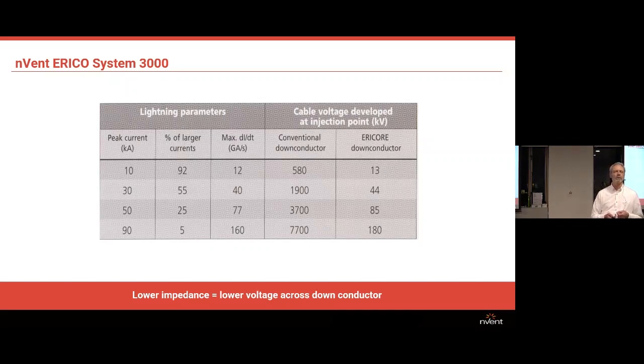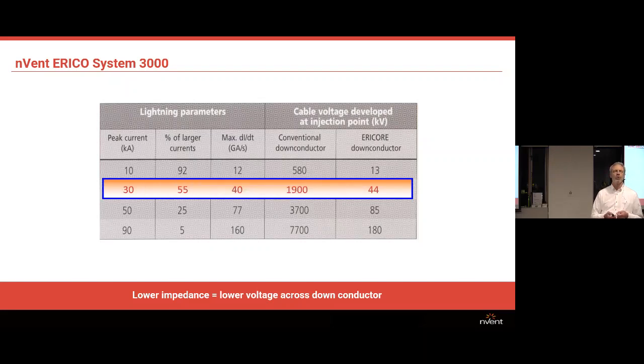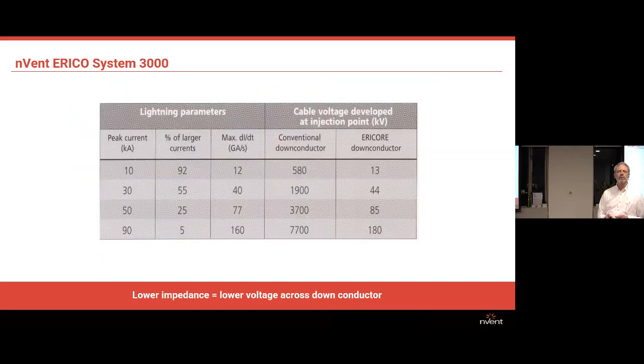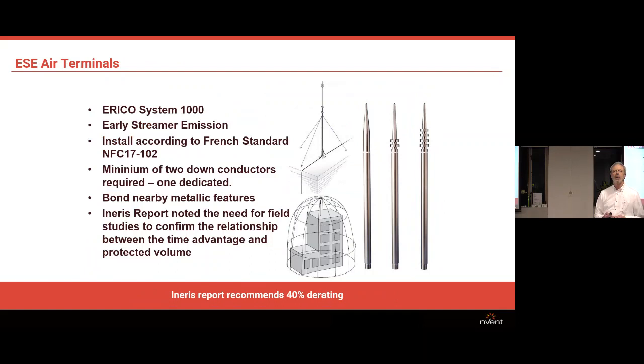And you can see here that if you have, for instance, a 30,000 amp peak current, that develops 44 kV at the top of the down conductor. However, if you're using a conventional down conductor, which is this sort of thing, then you're developing 1,900 kV. So there's a tremendous amount more voltage up there. And that's the benefit of the design of the high voltage cable. If I just go back to that system, we do supply that system with that high voltage cable, so we only need one, and it becomes an isolated system that can protect a large building. And so it is a convenient means of protection if you need something like that.